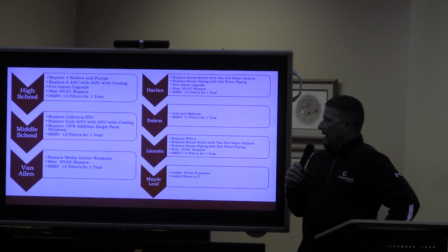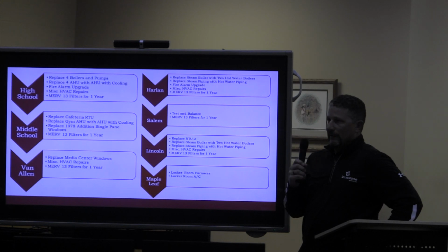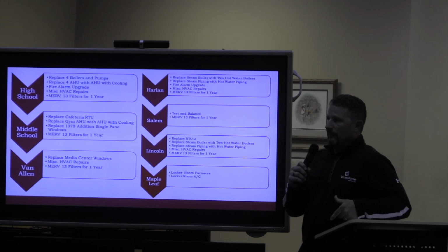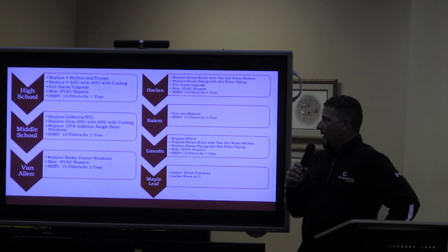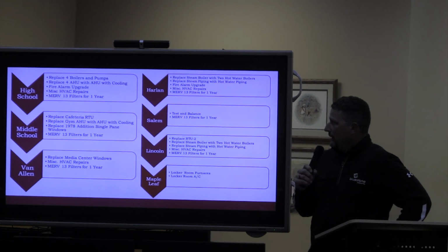Another thing that's under a bunch of these different schools is filtration, again as part of ESSER, to improve indoor air quality. Most filters in HVAC equipment are MERV 8; MERV 13 is a higher level of filtration, and that cost can be part of the ESSER funding.